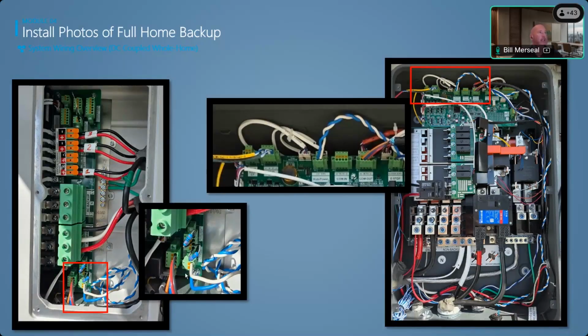When you have a hub, you'll see the COM out — I'll use the middle picture here. The COM out connects to the COM in. If you've got a second inverter, the COM out on that inverter goes to the COM in on the second inverter, and so on down the chain until the last inverter. Whether your last inverter is number 1 or number 4, the resistors have to go into that last one to say, this is the last one — communication stops here. This is where it creates the circuit and everything communicates properly. That's why it's super important.